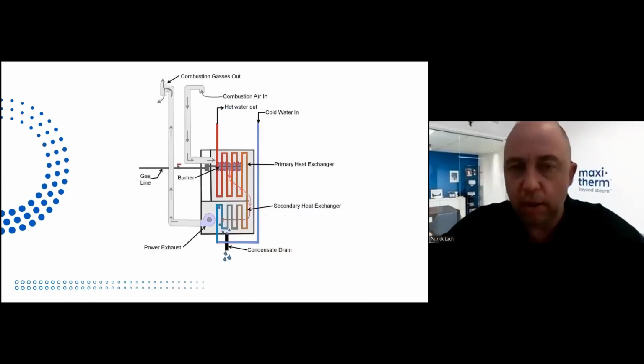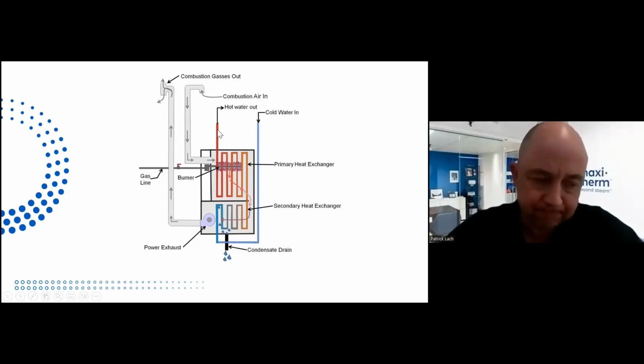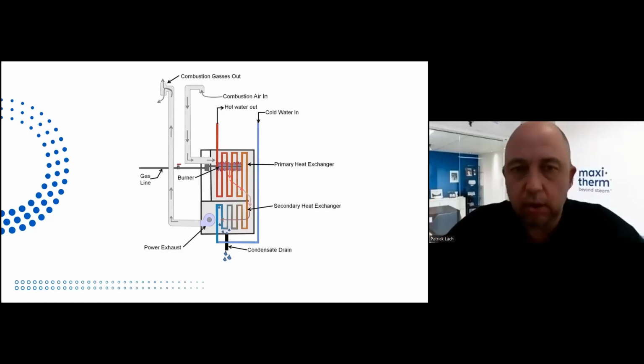So this is our number one competition, a condensing natural gas boiler, right? And this is the flue gas exhaust. We all know that the dew point of the flue gas is 140 Fahrenheit. So in order to condense that flue gas, you need a cold temperature return under 140. So that's why we want a low temperature set point. In today's world, a low temperature set point makes more sense because we want heat recovery from the chillers. We want to introduce geothermal, solar, and all kinds of benefit of using those renewable energy.